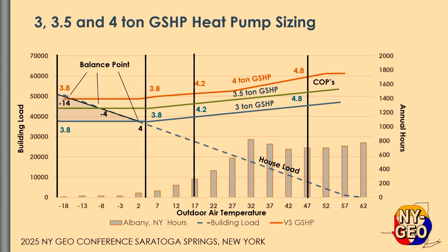And then, of course, it stays solid all the way through here, because once you hit 100% runtime, your loop was sized for that particular operation, and so you really just keep humming along at that same performance, no matter what the outdoor temperature is. So we maintain that 3.8 all the way through that, and so that's really a good thing.